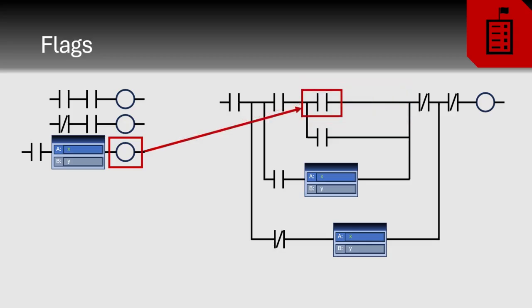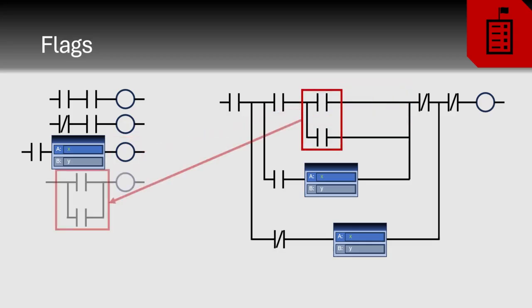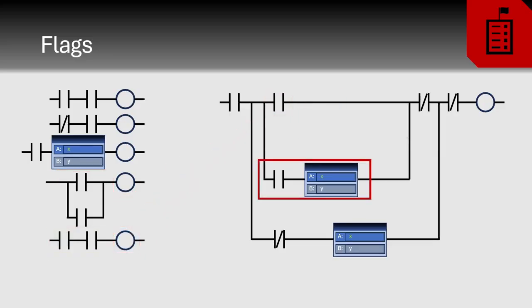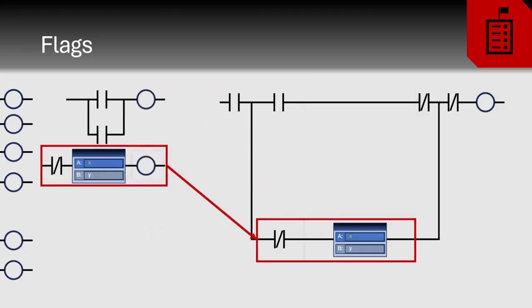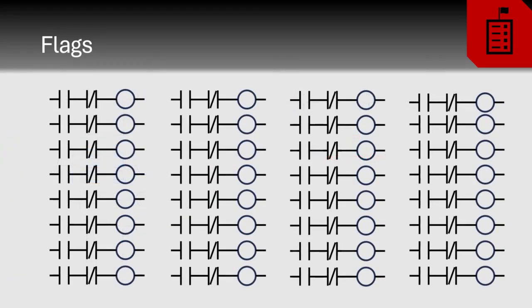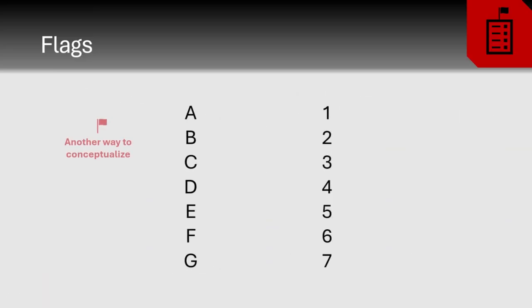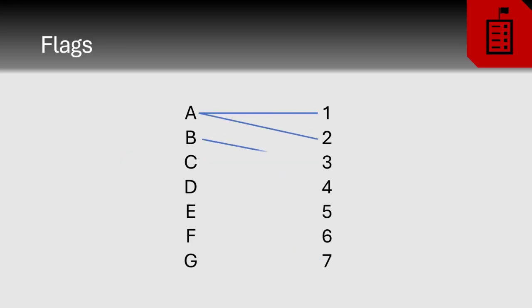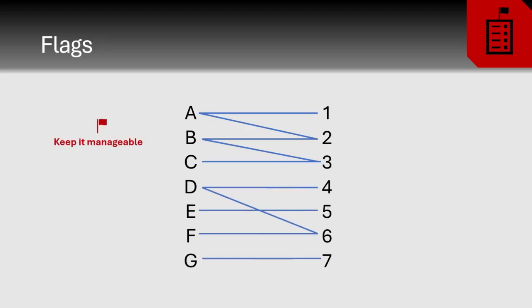Once branches are simplified, a single flag can replace the OR gate logic. This process is similar to solving series parallel resistor values for electrical circuit calculations. This is a very well-defined brute force approach. Each chunk of logic is easy to comprehend. Additionally, it is easy to edit conditions without affecting logic elsewhere. Another way to think of this is simplifying connections between points. Cross-referencing fewer connections allows quicker debug and easier comprehension.